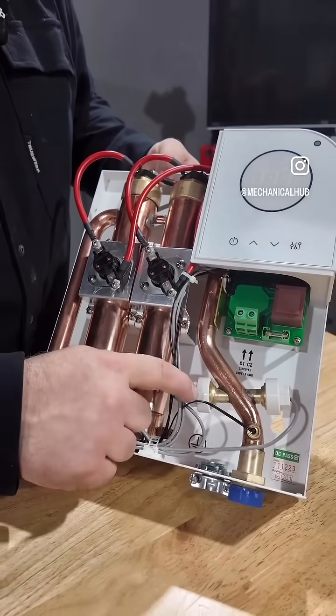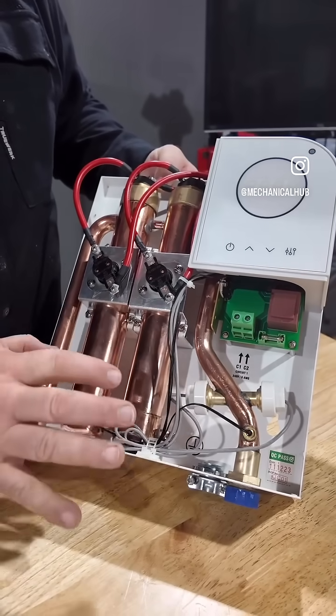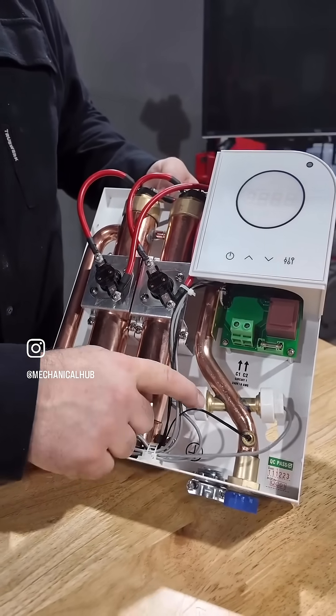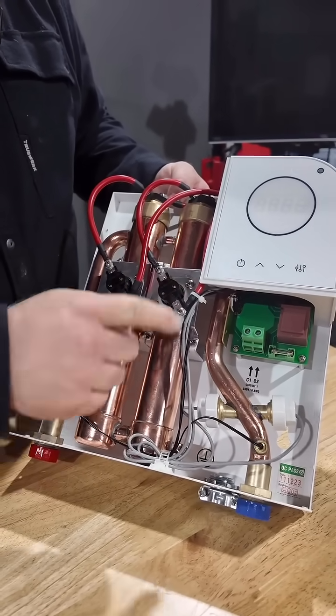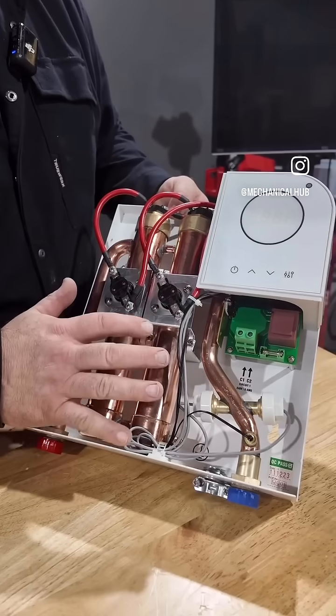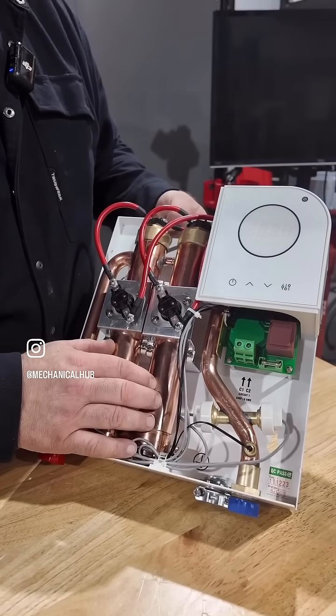It's a different kind of flow sensor — it's called ultrasonic. There's actually nothing in the flow path to impede flow or to collect minerals, which is important. The ultrasonic flow sensor will activate the heating elements through the control. It'll also tell the unit whether or not it's dry firing, detecting air or lack of water, and it'll shut down the unit to prevent ruining the heating elements.